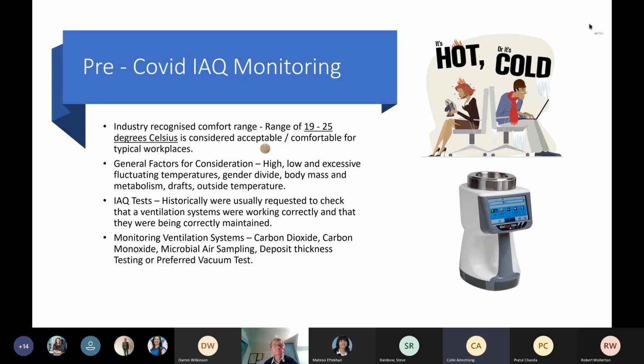And carbon monoxide. We're asked to monitor that as well, just in case there are gas heaters that are broken or boiler flues. And then there's microbiological sampling, where they test for bacteria and fungi. Again, it's in the air. Going back to the HTM, the guy that writes that for the NHS aired his concerns to me and said, well, it makes no difference. Why are you sampling the air for that? I think his exact words were, you could have the worst asthma in the world and you're not going to catch anything from the readings you're getting on those agar plates. So it's quite an interesting one. People do ask us to take air sampling, and they do ask us to take samples using the plates on AHUs, and often ask us to clean them out. But for us, it's a bit of a grey area. I can understand why people do it, but the NHS, as I said, who are unbiased, say no, don't do it. But I can understand why people do it.